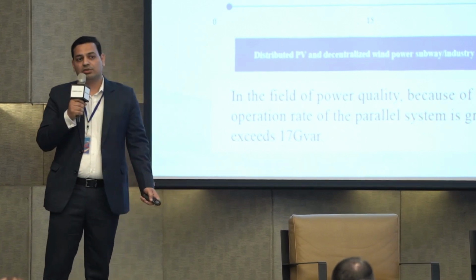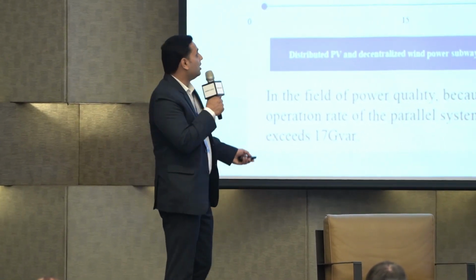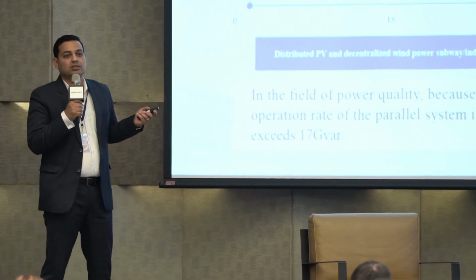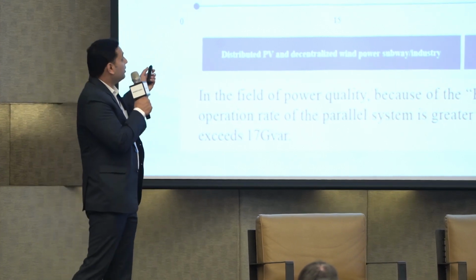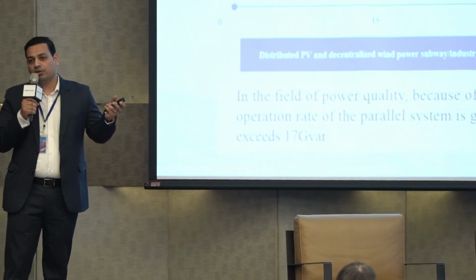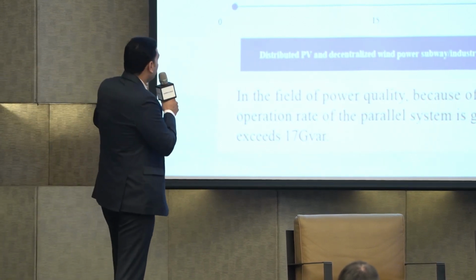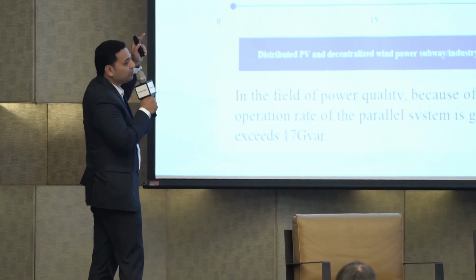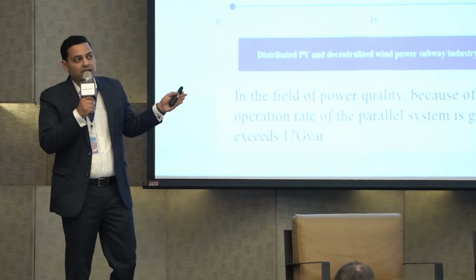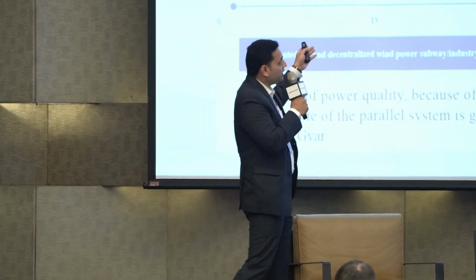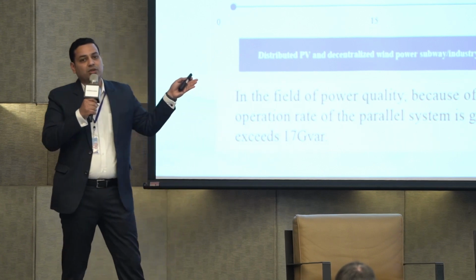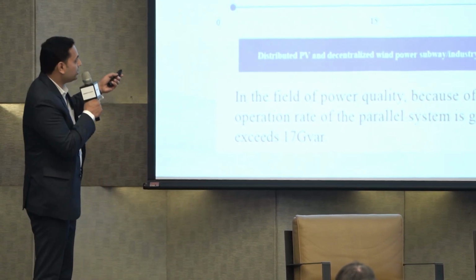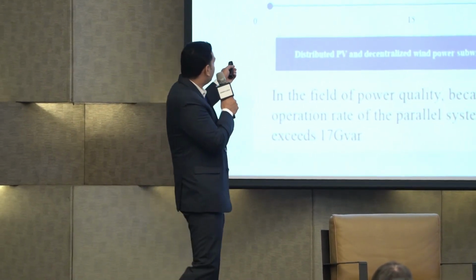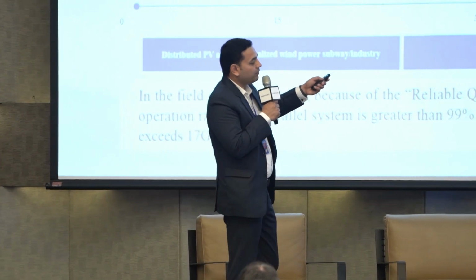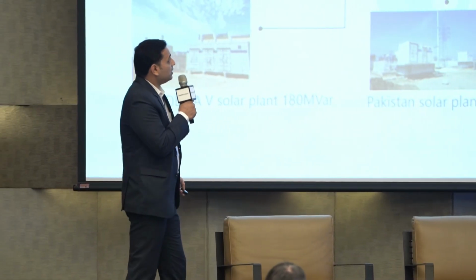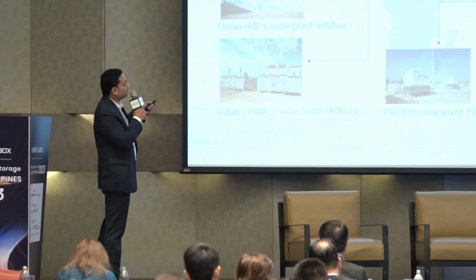Coming on to the power quality solutions for solar projects or wind projects, we are manufacturing static VAR generator to support the grid voltage, where we have 2 different kinds of solution, indoor and outdoor, air cooled and water cooled. And the voltage levels we can supply from 3.3 kV, which goes up to 35 kV. Means rather than feeding through the inverter for reactive power, you can utilize this device at your 33 kV or 35 kV MV bus level. So it will be a centrally located solution. We have capacities starting from 15, which goes up to 100 MVR single unit. Some of the references, we have utilized this SVG at different parts of the world.